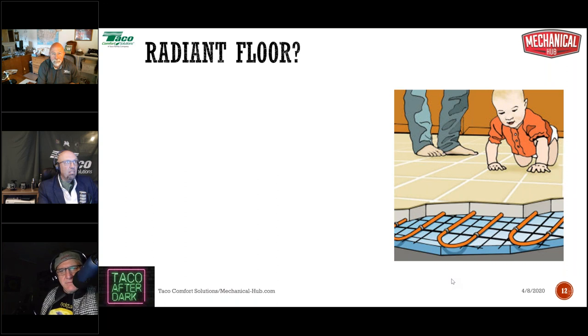Dave, go ahead. I would say the lowest temperature that you can get out of it. So you're going to supply the lowest water temperature and therefore keep your boilers off longer, modulate that water temperature down low, and you've got a lot of freedom with it after that. So that would be the one advantage to a slab style system. And of course, you get the tubing patterns wherever you want. Okay, very good. Rick, what do you think?